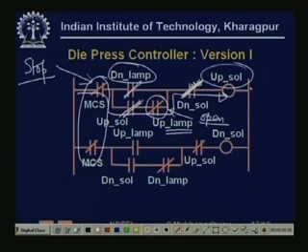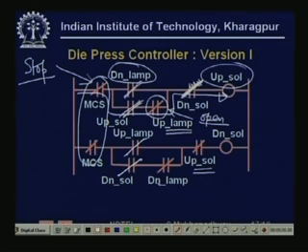So now the up solenoid becomes zero, so therefore this is closed, and the up lamp has glowed. So this is now closed. So immediately the down solenoid will now get supply. And when the down solenoid gets supply, this is closed, and the down lamp is anyway not excited. So therefore it will start coming down, and then the up lamp will open. But still there is a path in this way, and the down solenoid will keep getting supply, and so the press will keep coming down under hydraulic pressure.